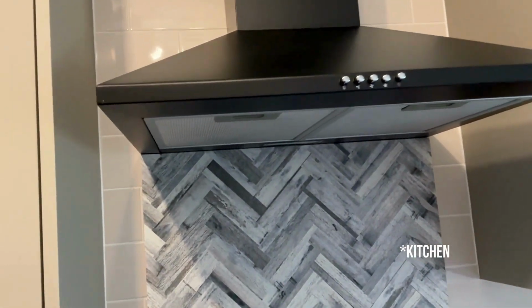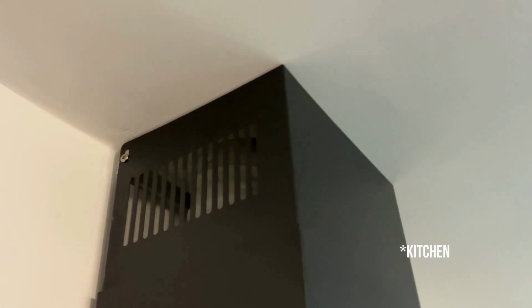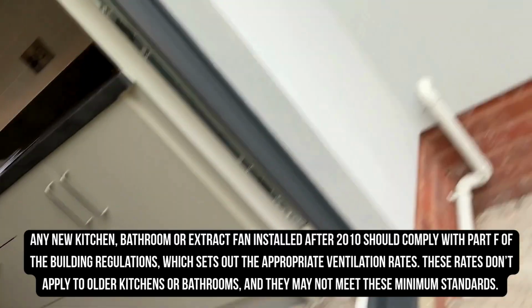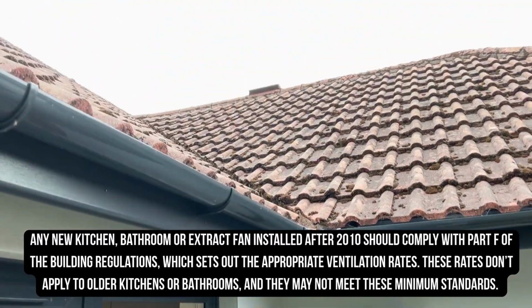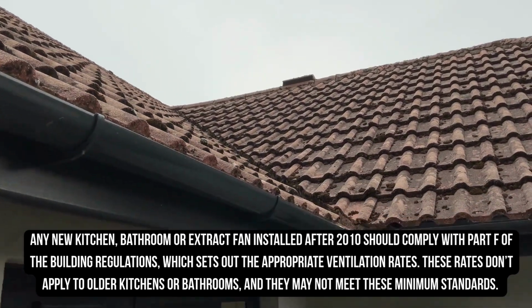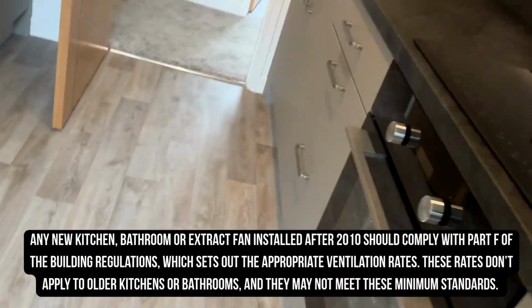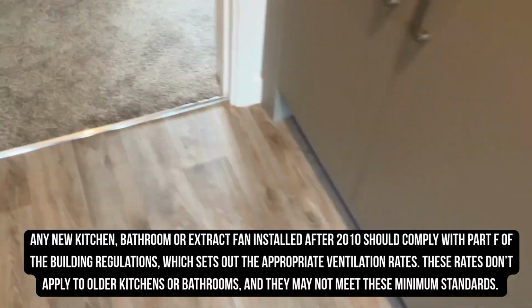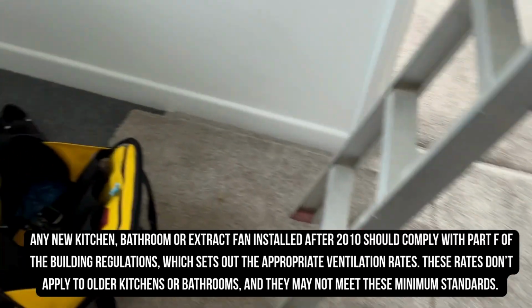So this is our penultimate example. Again, got a cooker hood. This is in a brand new kitchen in a house that's being marketed as having been refurbished to the highest standards. We can see that it's ducted into the roof space. Sometimes these cooker hoods don't need to be, they can just be recirculated and they just filter some of the fats out of the cooking. So stepping outside, I can see that there is a ridge vent up there, so there's a possible point where it could be ducted to, but we don't want to be assuming on these sort of surveys. And if you've been watching this video, you can understand why seeing a vent outside isn't necessarily proof enough that that extractor fan is venting and discharging to outside air.